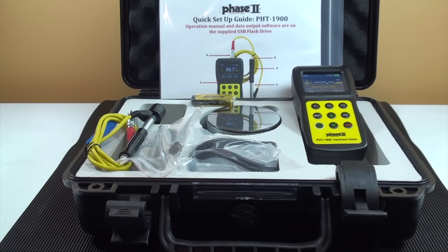The technology incorporated is based on the Leeb system of hardness. A carbide ball is spring loaded and impacts the workpiece with a given force. The rebound velocity is then measured and converted to a hardness value in Leeb, which can then be converted automatically and be read in any number of scales, which is selectable prior to testing.